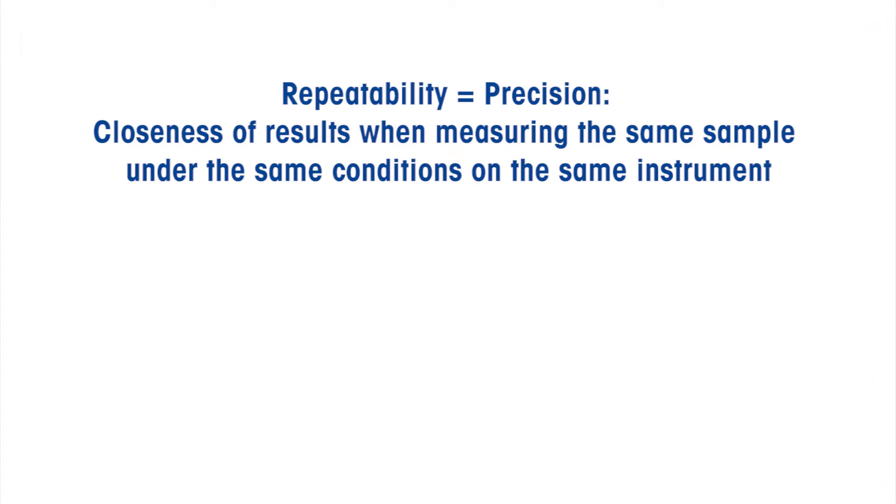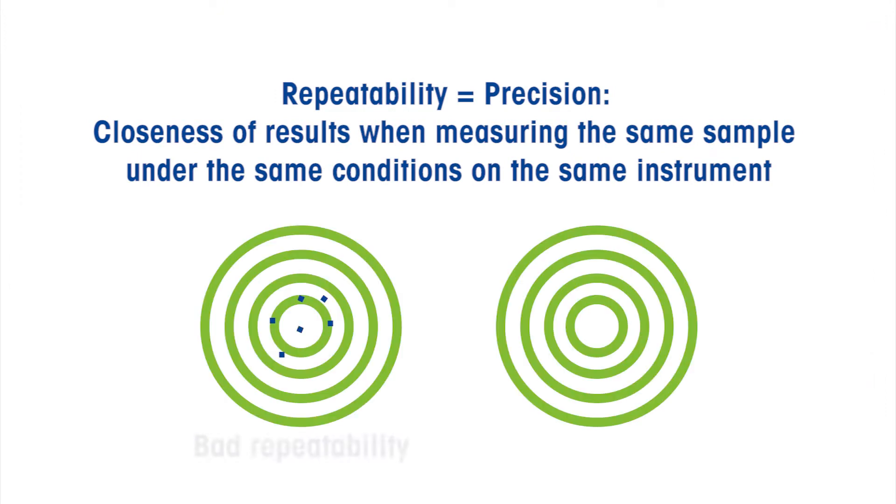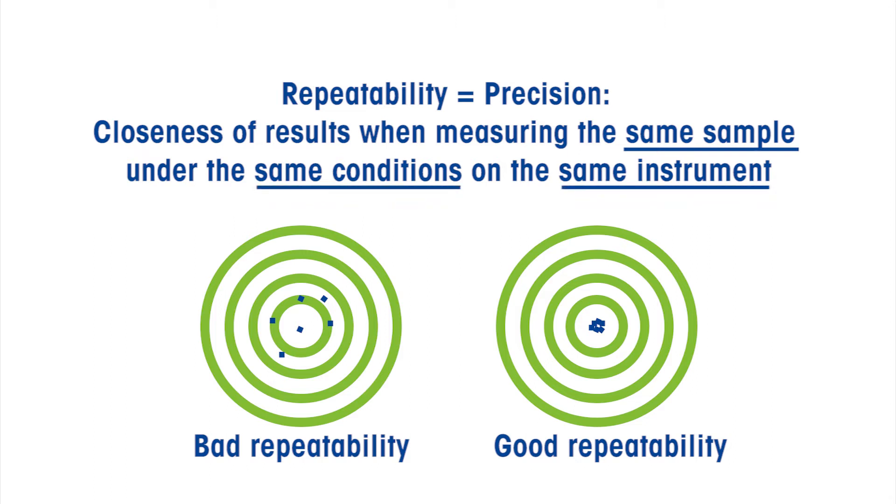The most important parameter for a moisture analyzer is repeatability or precision. It describes how close together the moisture content results are when the same sample is tested repeatedly under the same conditions and on the exact same instrument. It is expressed as standard deviation in the datasheet.